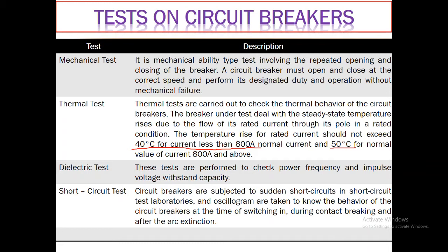Otherwise it will cause unwanted switching operations of the circuit breakers, and may create unwanted switching over voltages which are unhealthy for the insulations of subsequent equipments. So in today's lecture, my agenda is to discuss how the power frequency withstand voltage test is performed on the circuit breakers to assess the quality of insulation in terms of its voltage withstanding capacity.